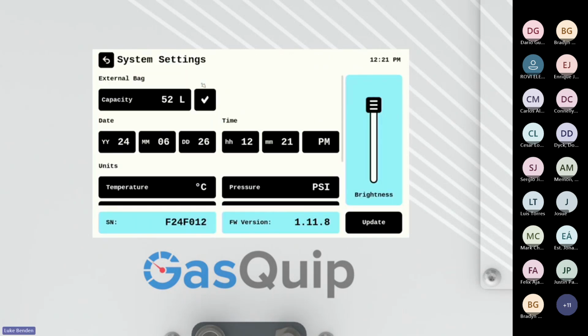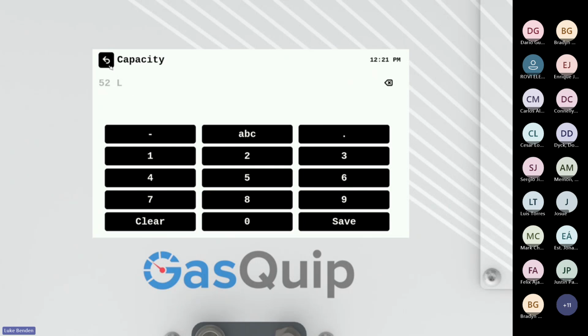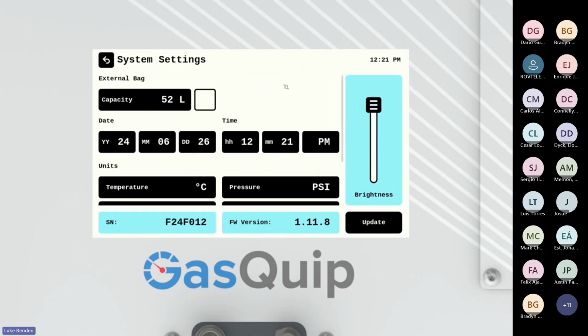The system settings, here we have a setting for an external bag, so we can check and uncheck that. Actually, I should have had that unchecked. I forgot to uncheck that, but you can check and uncheck this for whenever you plug in an external bag. And you can also change the capacity based on the amount of liters of gas the bag can hold. We have ours defaulted to 52 liters here because our bag that we have is a 52-liter bag. So that will also change the percentage of storage that'll show up on the main screen like we talked about.